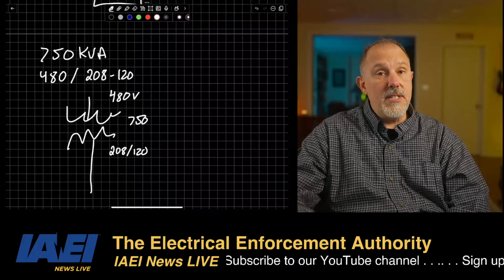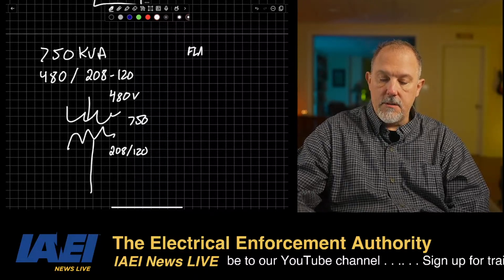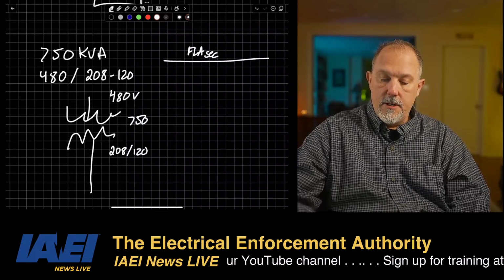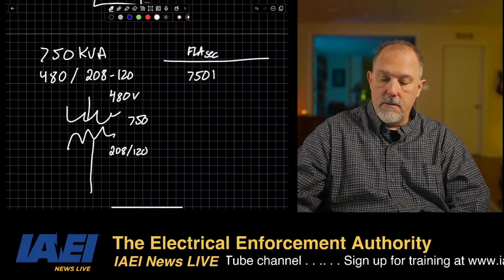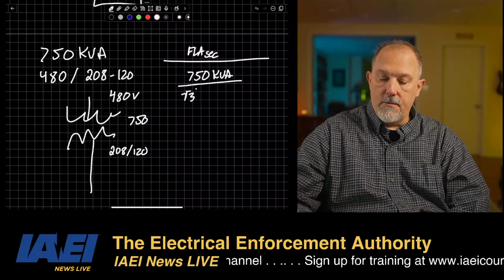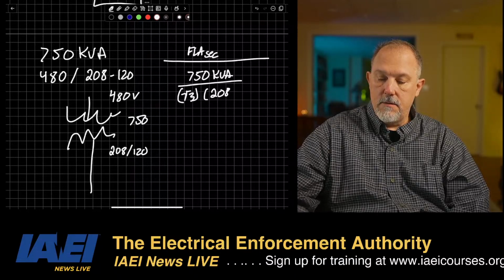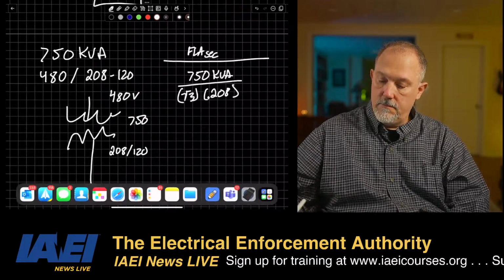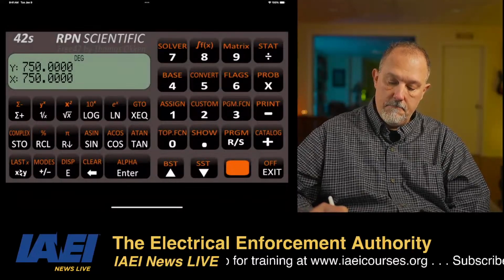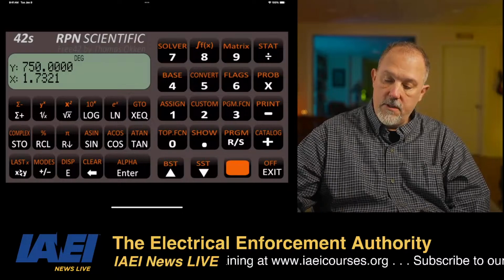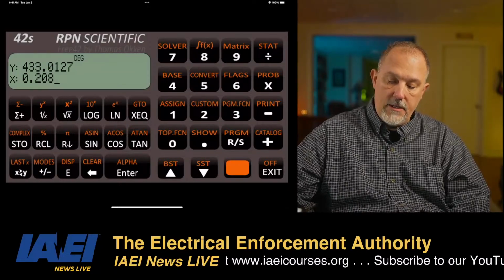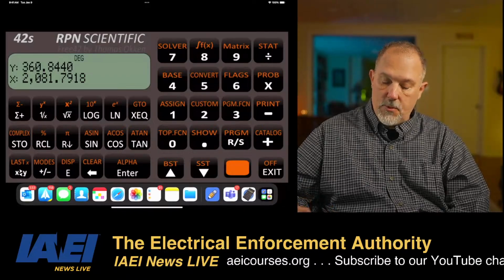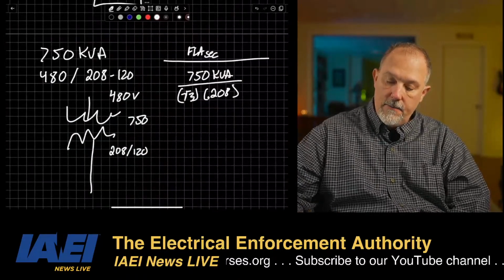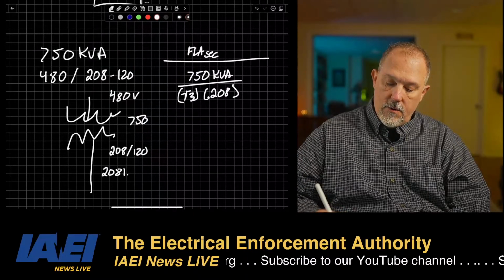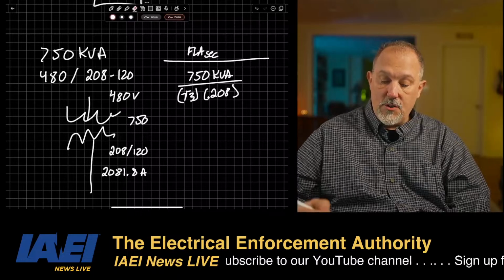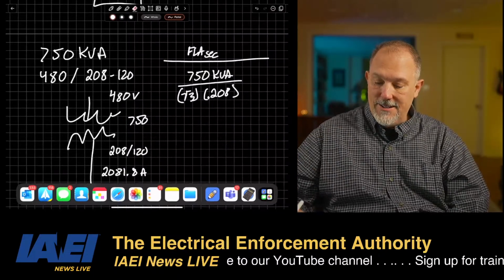So we'll just do the secondary currents, I secondary. So full load amps on the secondary is 750 kVA divided by the square root of 3, divide that by 0.208. 750, 3 square root, divide 0.208, divide: 2081.8 amps.